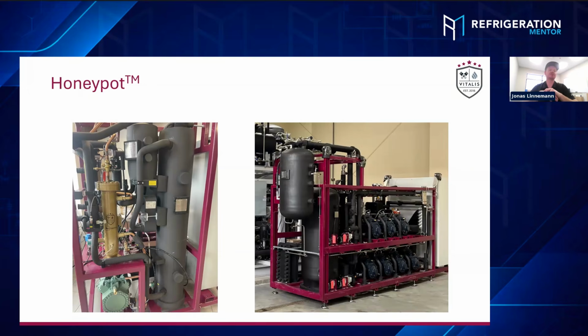For the initial filling, if you need to refill some oil after a day or whenever, you would just isolate the oil reservoir, and then you could even do that if you're quick while the system is normally running. Again, sometimes it's helpful to drain the pressure once that oil reservoir is isolated, to drain that pressure with the service hose into the suction line to be quicker and not lose too much CO₂. And once the pressure is drained, you either have these little pumps, they work to push in oil while the vessel is under a slightly lower pressure.